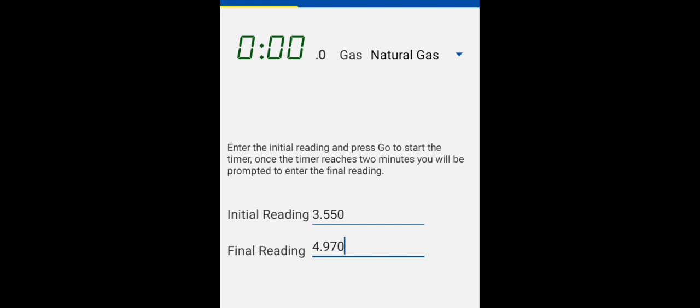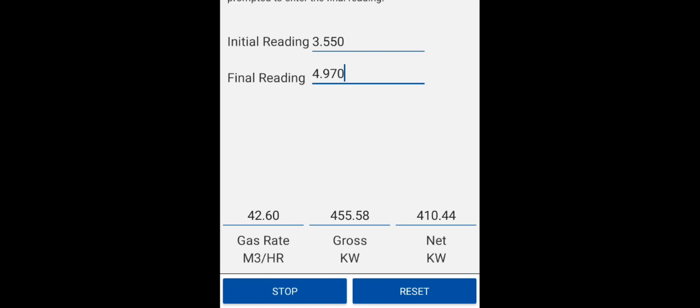I carried out a gas rate on the meter. You can see I put a decimal point in here, and then you have the readings of the boiler in high fire, and the gas rate is calculated using the Anton Sprint app.